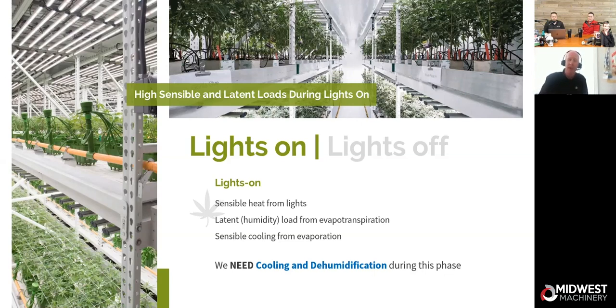So at the beginning, when the plants are going in at, say, early flower, you don't have as much water consumption, so you don't have as much evaporative cooling. So you have a higher sensible with less latent. But over that 8-week flower room period, your sensible cooling need is going to go down and your latent moisture removal from dehumidification is going to go up. So it's dynamic, it's changing, and it changes as the plants change.